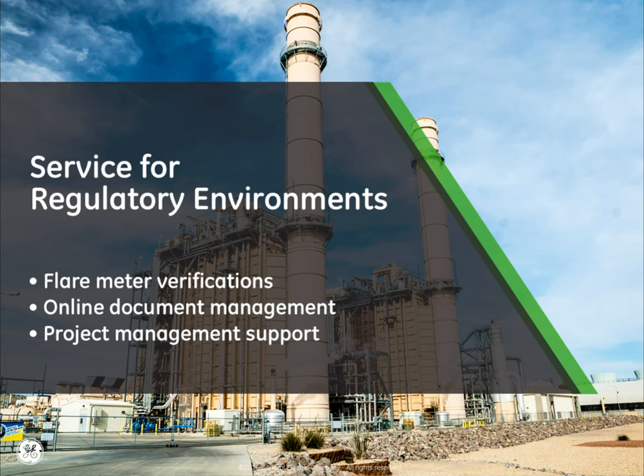In one instance, GE has partnered with a major international oil company to service all regulatory flares in its U.S.-based operations. Faced with the current regulatory pressures of NSPS Subpart JA and the forthcoming requirements of the refinery sector rule, this particular customer sought to outsource its flare service liability. Now, each of its regulatory flare meters are verified by an assigned GE FSR on an annual basis.